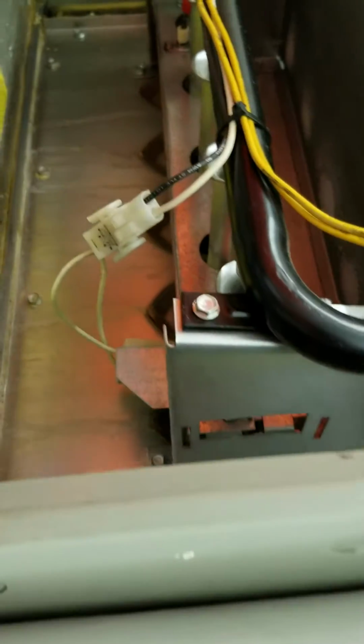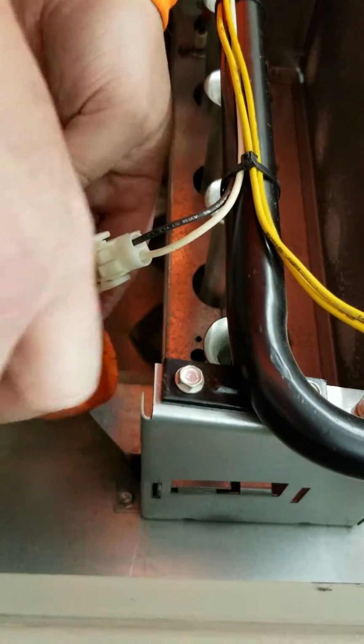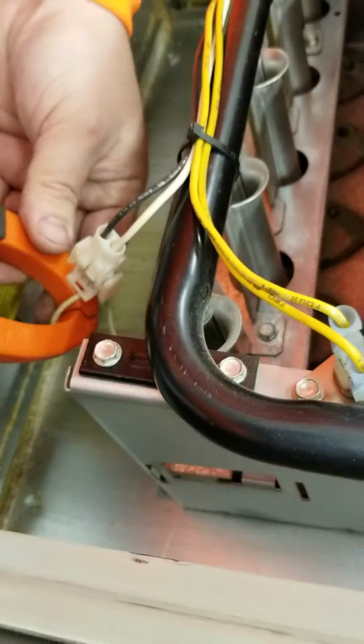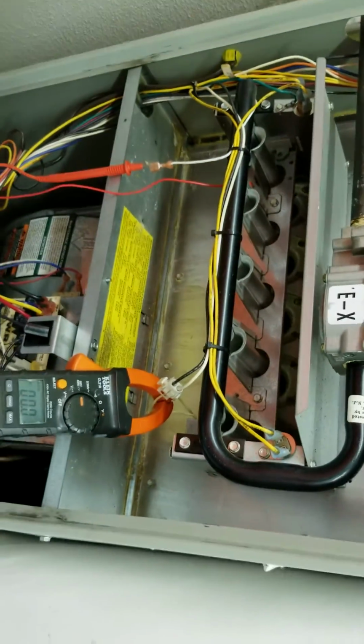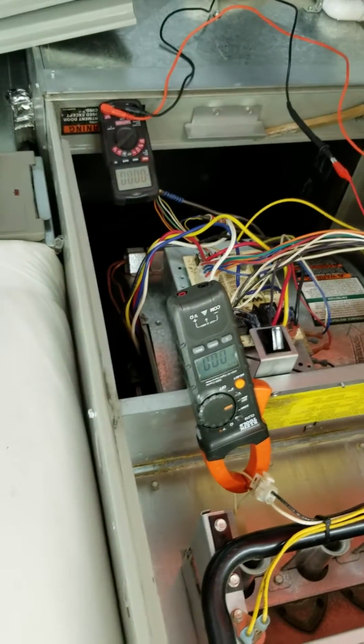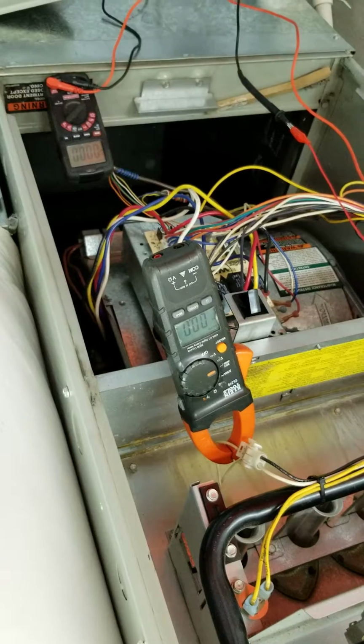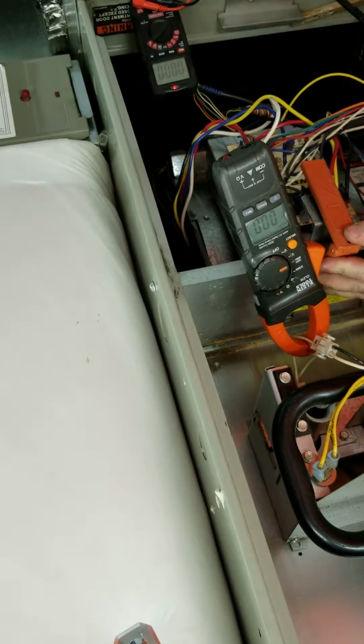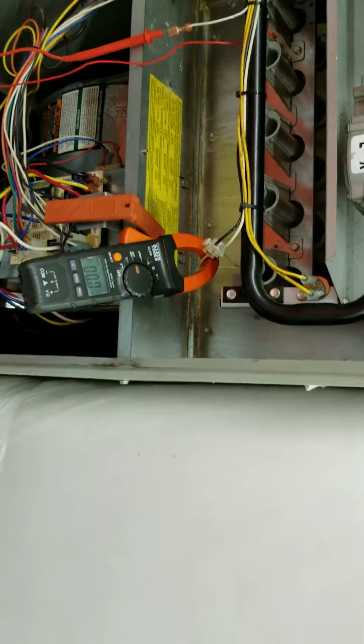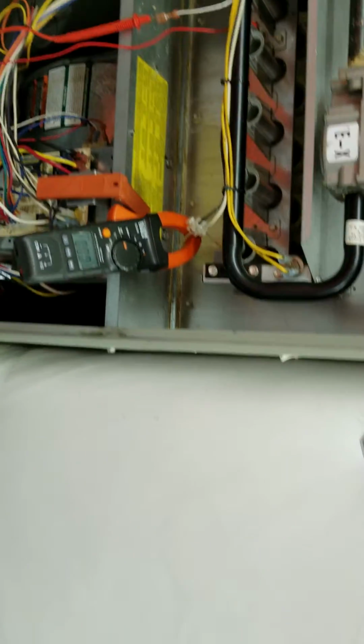Now you want to take your amp meter, and the first thing you'll want to get is the hot surface igniter current. And there, so now your 2 meters are hooked up. So the next thing would be to take your safety switch holder and, yep, right there, so that your safety switch can be energized. And thermostat, now because we've turned the thermostats down, let's go back and turn the thermostat up.